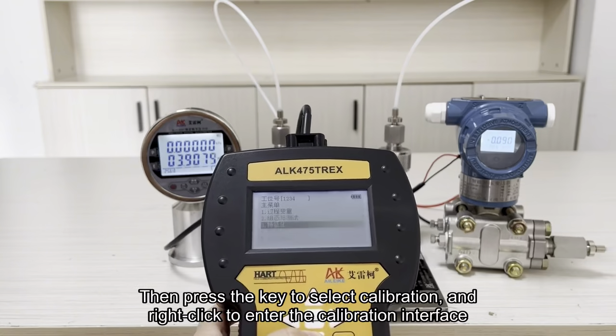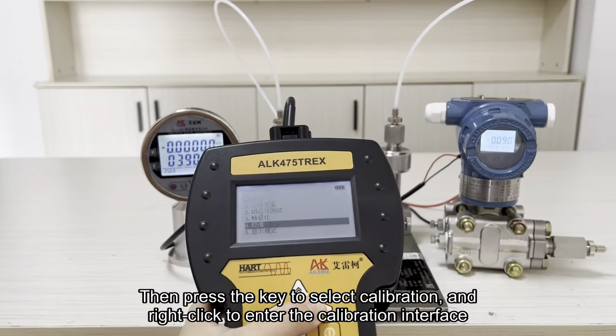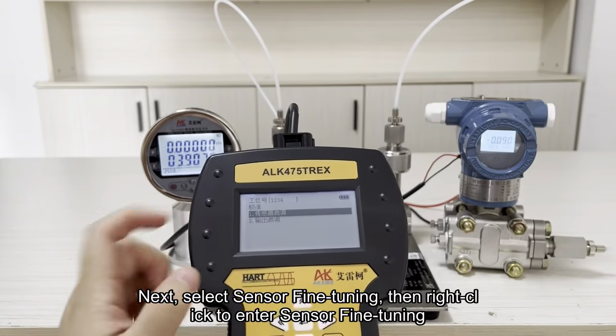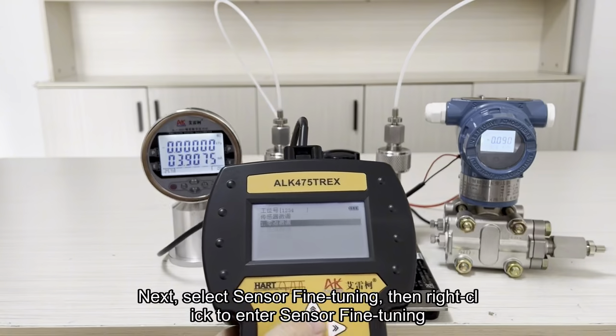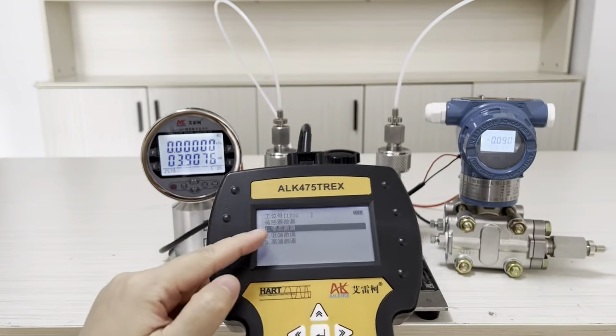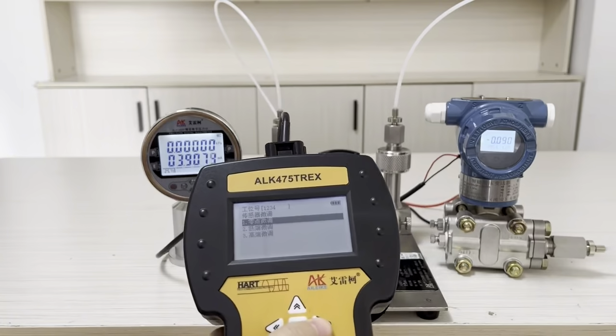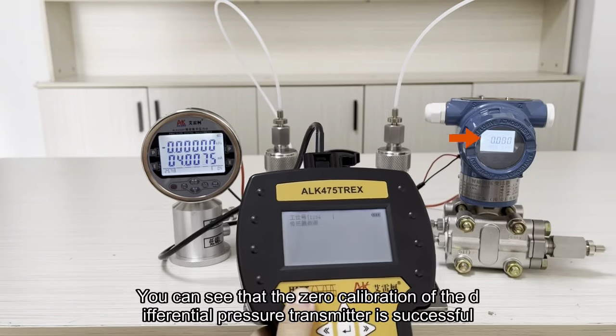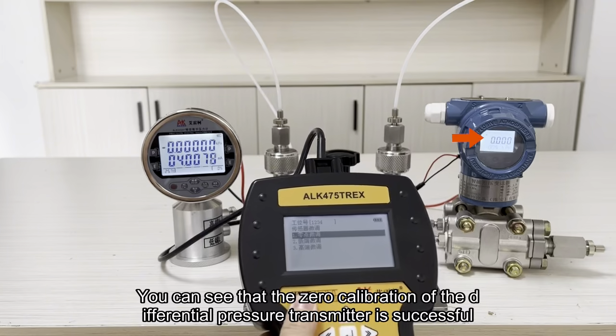Then press the key to select calibration, and right-click to enter the calibration interface. Next, select sensor fine-tuning, then right-click to enter the sensor fine-tuning interface. Then select zero fine-tuning. Finally, right-click to confirm. You can see that the zero calibration of the differential pressure transmitter is successful.